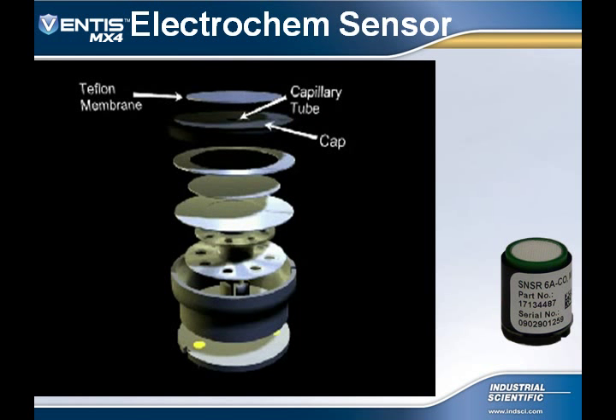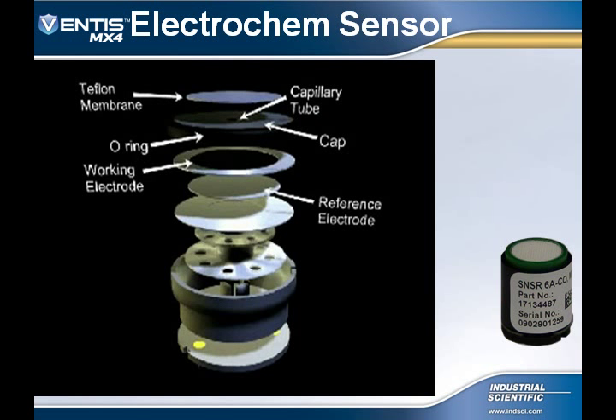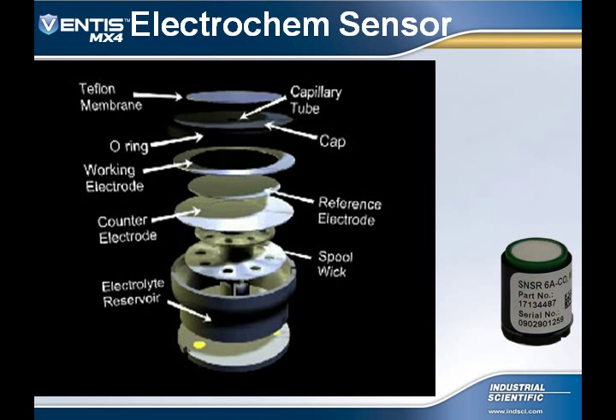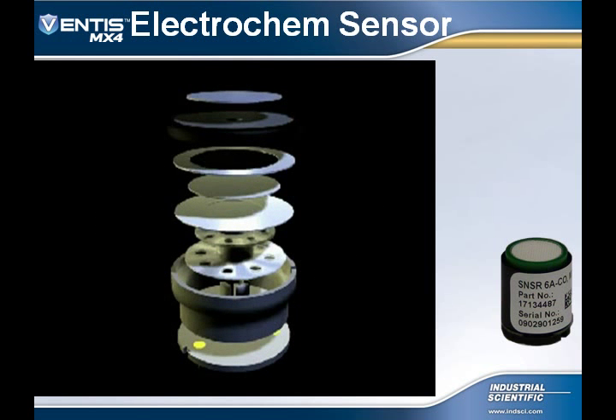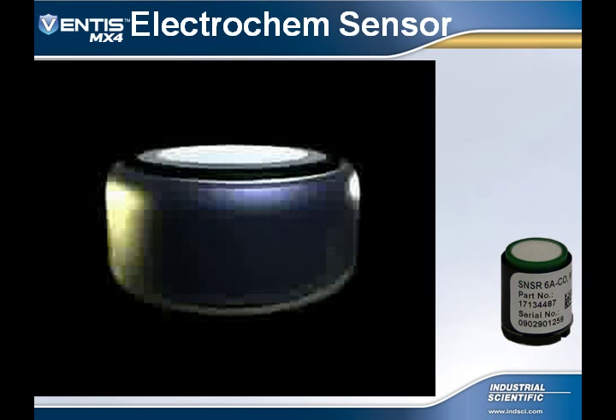Going down even further, there is an O-ring, which holds the parts of the sensor together. Underneath the O-ring, you have your working electrode, your reference electrode, and counter electrode. These electrodes are made of precious metals. These different metals give the chemistry needed to detect the specific gas that the sensor is made to detect. As well as the electrodes, you have the spool wick and then the electrolyte reservoir.